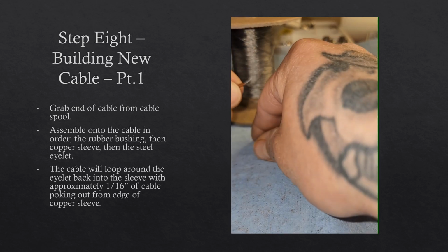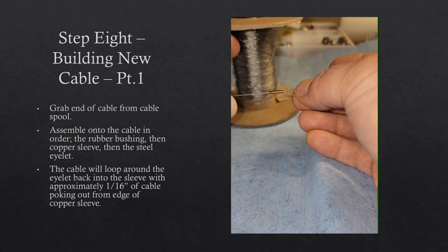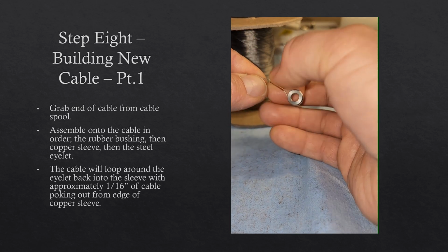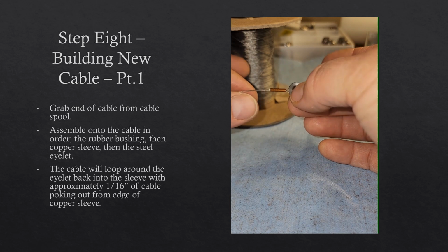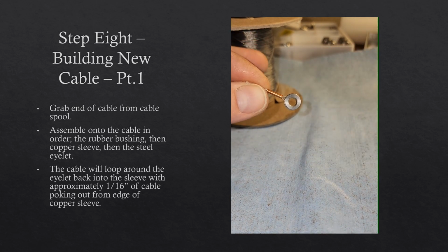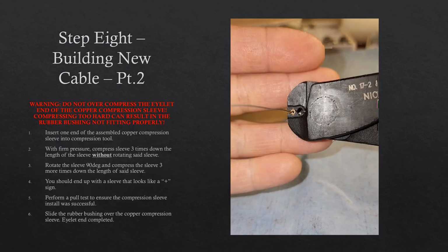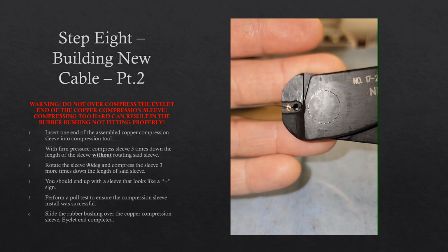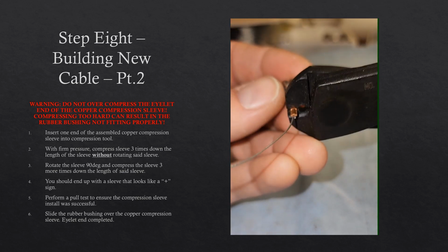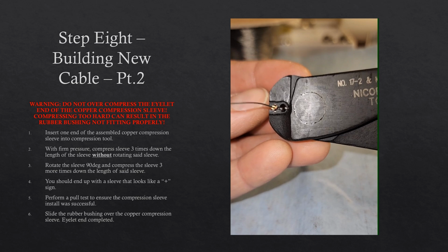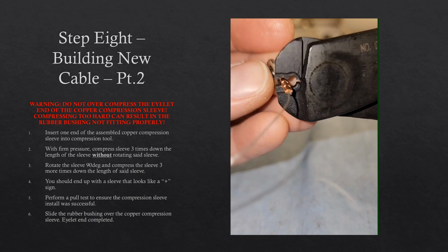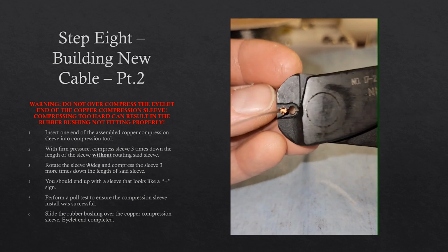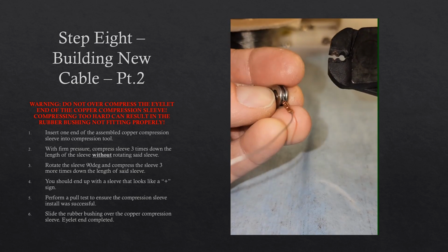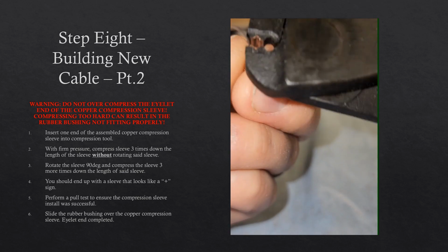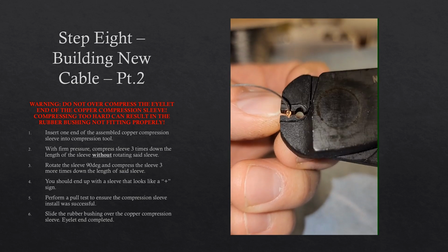just like that. Then we're going to take the steel eyelet and slide it up until it's snug on there. It doesn't need to be super tight, it just needs to not come off. Then we're going to take our compression tool and compress it 3 times the length. So 1, 2, 3 different times down the length of that compression sleeve in the same direction, same orientation, right? Then we're going to rotate that compression sleeve 90 degrees and do the same thing again. And what we're trying to create is like a little plus sign.